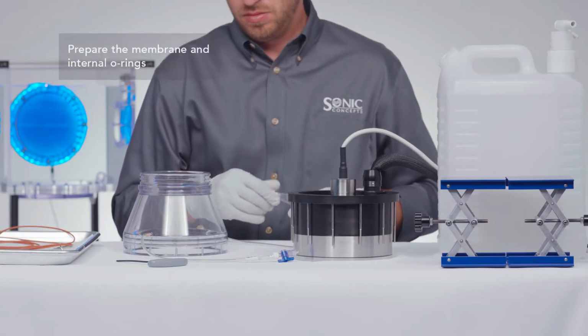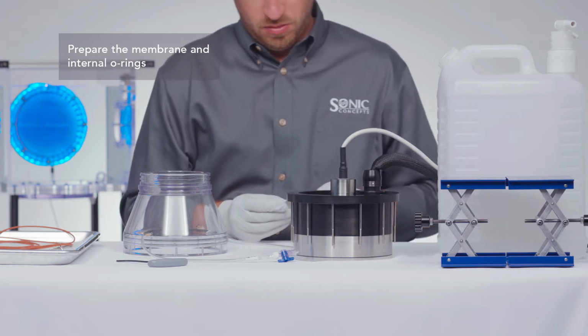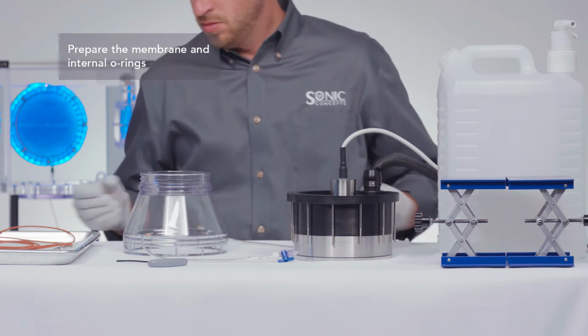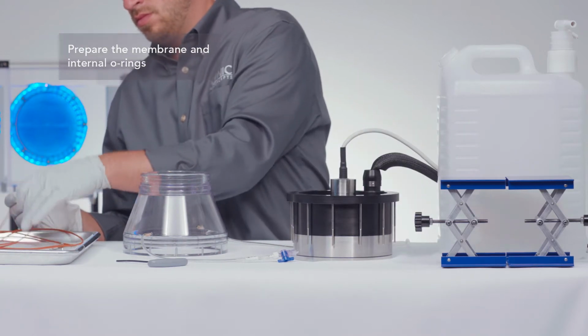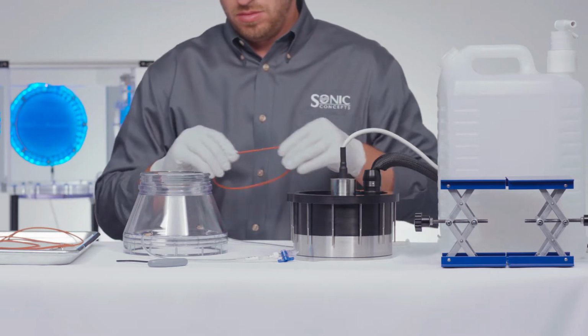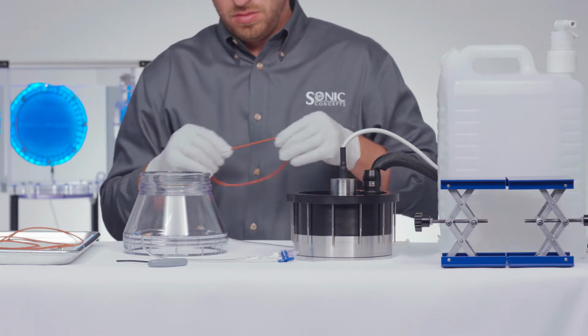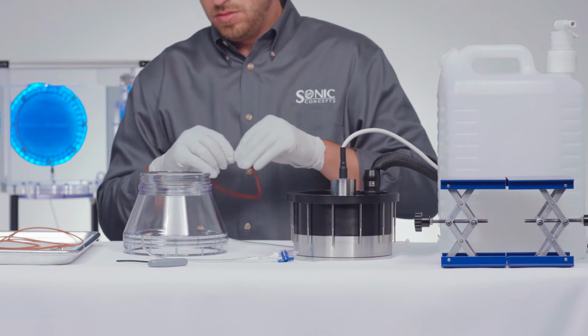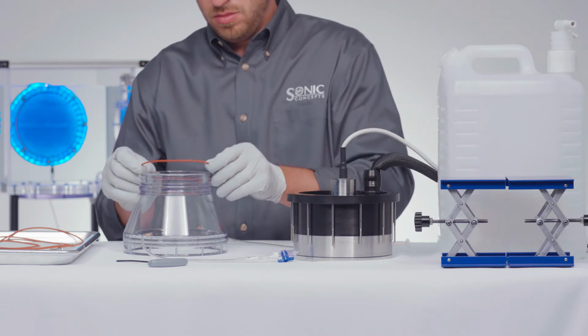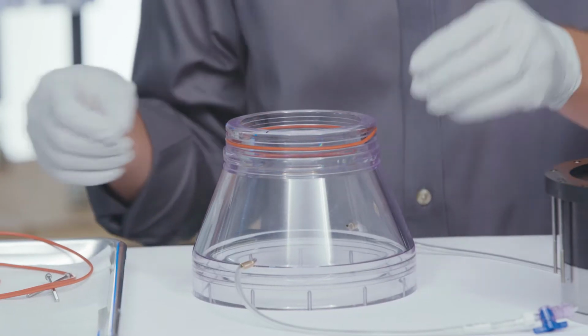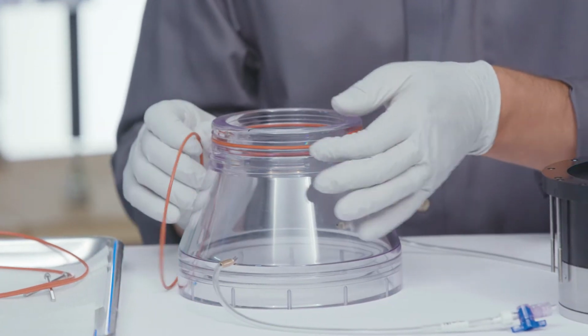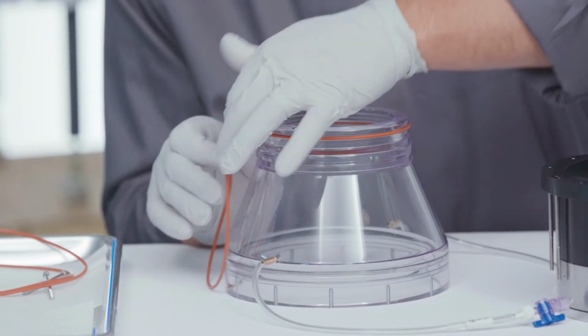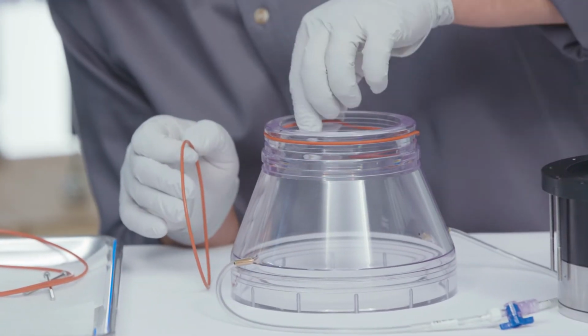To ensure a watertight seal and a lubricated frictionless interface between the CT-300 coupling cone membrane and membrane retention ring, dispense a small amount of O-ring lubricant to your fingertips and thoroughly coat both membrane O-rings. Once lubricated, install both O-rings. Thoroughly lubricate both internal O-rings and install until properly seated with the coupling cone's inner grooves.